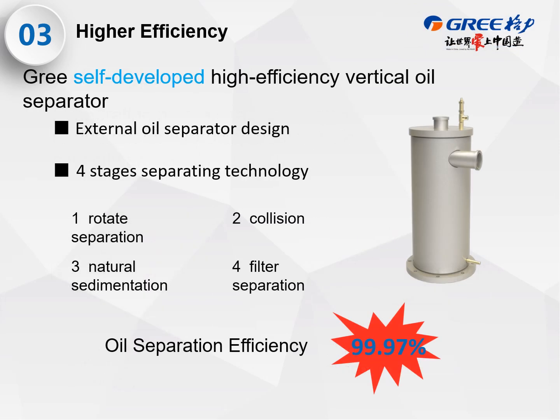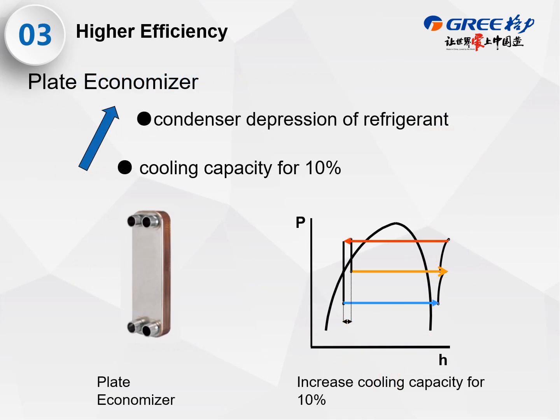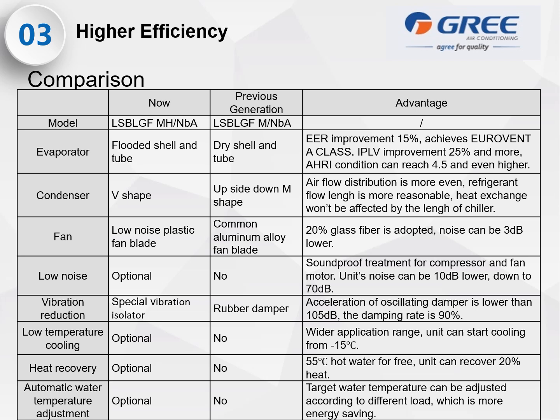The Gree self-developed high-efficiency vertical oil separator uses an external oil separator design with 4 stages of oil separation technology, and the oil separation efficiency is up to 99.97%. For the plate economizer, it uses subcooling of refrigerant, and cooling capacity is improved by 10%. For a development or manufacturing plant that requires a plate economizer, it is possible. All you need to do is request it from us. Here is some comparison between the previous generation and the recent design of air-cooled screw chiller.